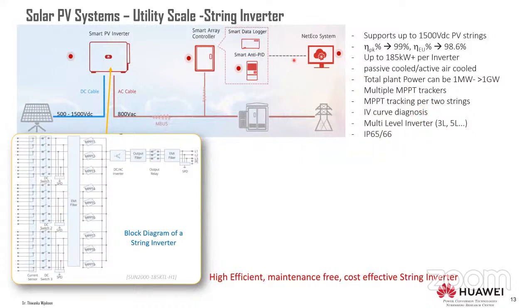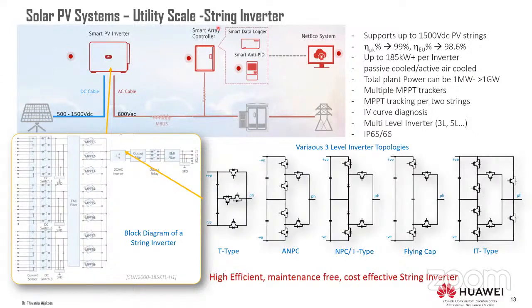These inverters are typically multi-level. A typical internal structure is down here. You have EMI filters on both sides. You have maximum power point trackers, which are DC-DC converters, and then the main part is the inverter, then a filter, and then you have the chance to disengage by relays as well. Typically these DC-AC inverters are multi-level. Typical structures of 3-level inverters you can see here, a whole spectrum of topologies. This is a single phase circuit diagram, let's say.